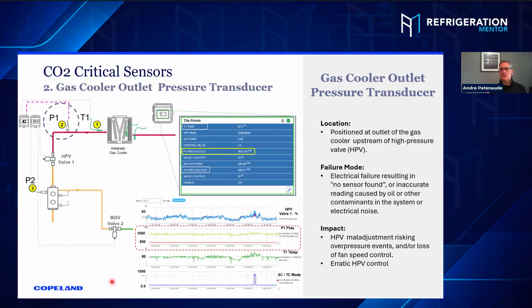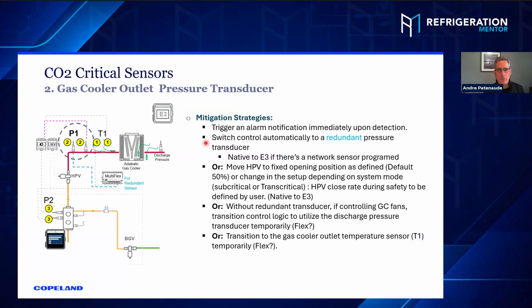And with that transducer, again, that same screen, you can find out what it's doing. You can find out what percentage the valves are opening and closing, high pressure valve, bypass valve. So with Copeland, valve 1 is always the high pressure valve and valve 2 is always the bypass valve. Okay, so that's one thing to note when you're looking at the E3. And from a mitigation standpoint, this looks very similar to temperature one, right? If you've got a P1 pressure transducer that fails, boom, alarm sent. Second, switch automatically to a redundant sensor if you have one. Yeah. Or if you don't, again, you can default the high pressure valve to 50% open, or you can change that slightly when you're doing your setup in the E3.